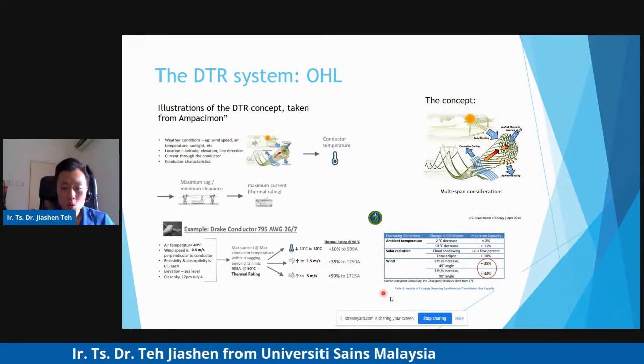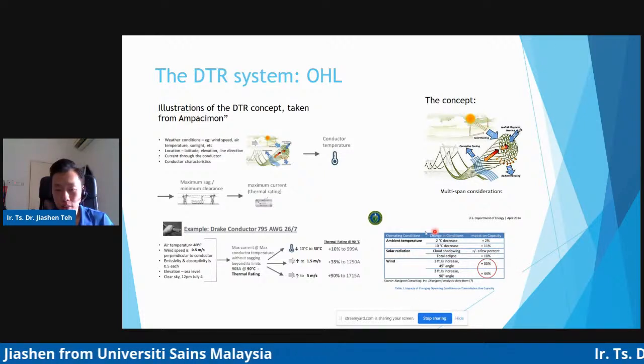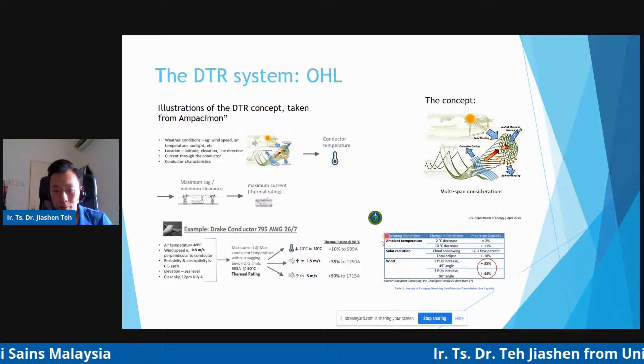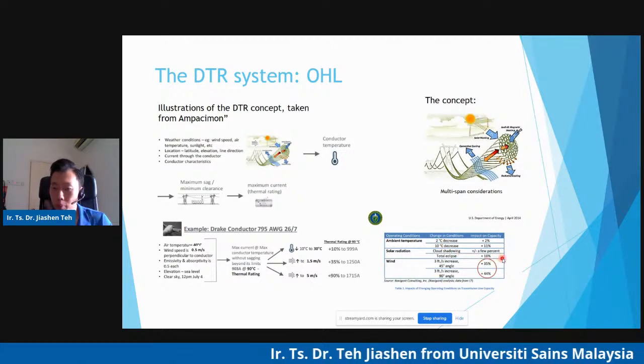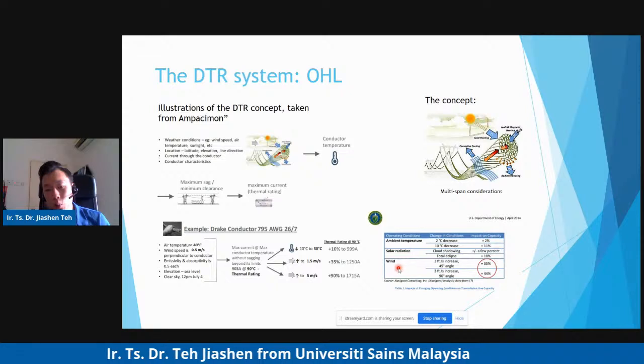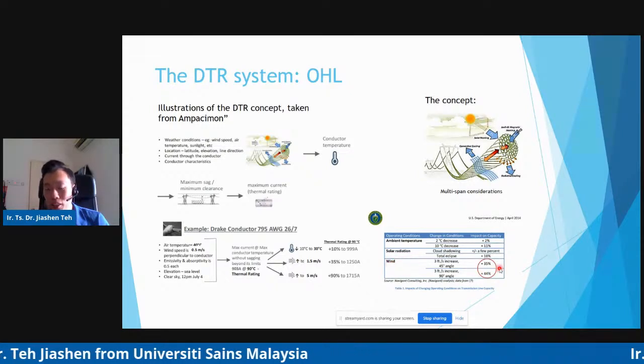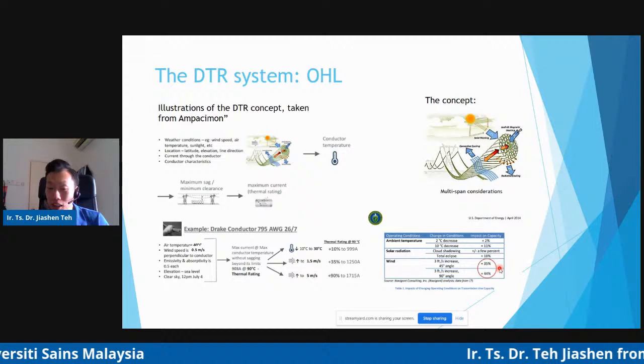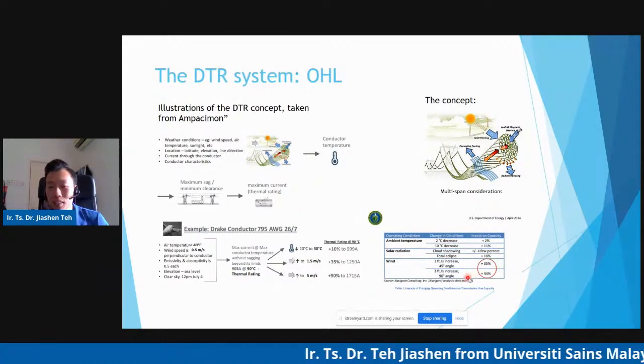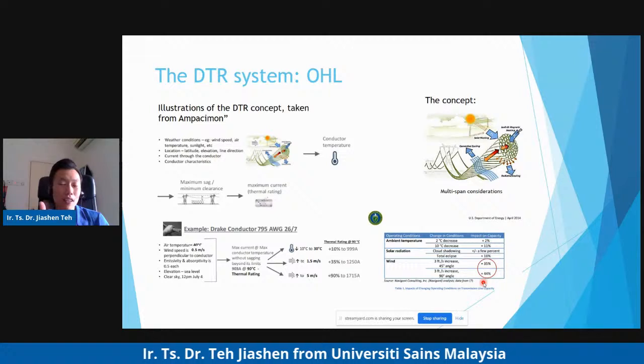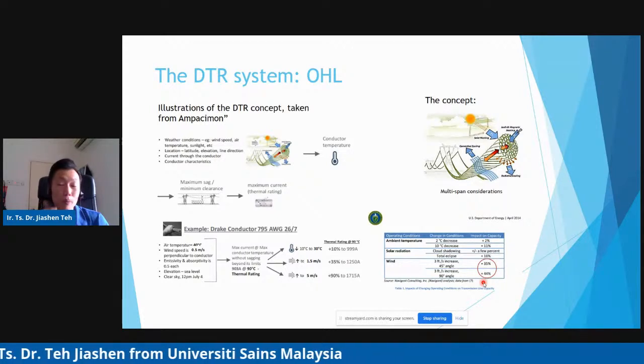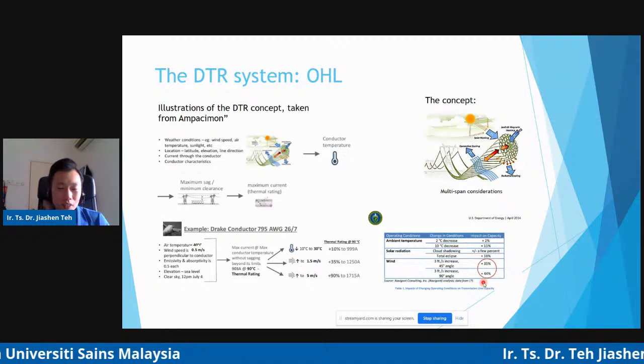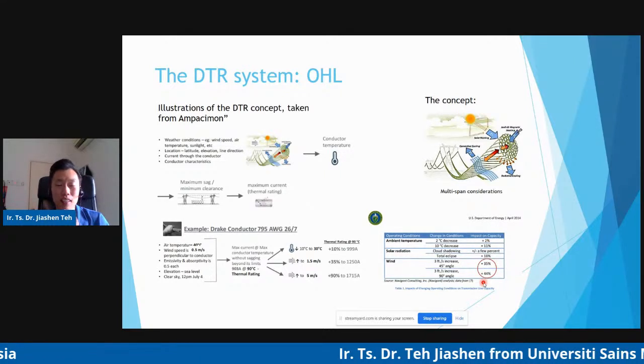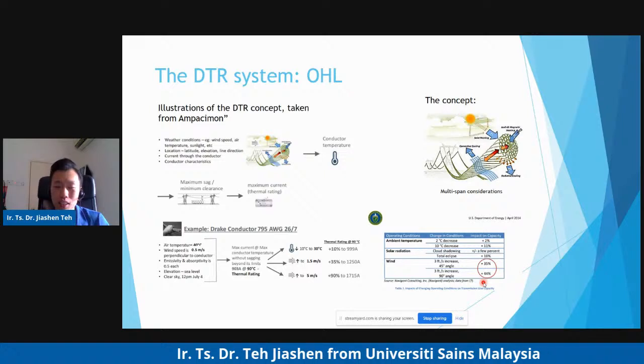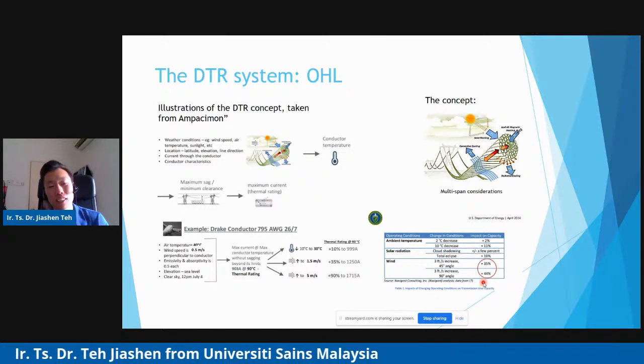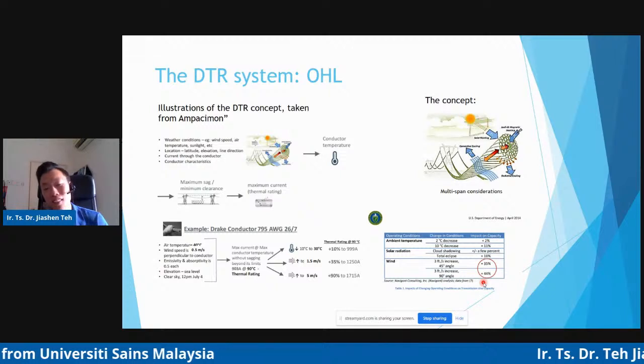I want to point out a study from the U.S. Department of Energy. It shows that with wind considered, we are able to increase line rating capacity by up to 35%, and in certain cases 44%. That represents a significant increment in the underlying unused rating of the conductor, just by deploying the right technology, which in this case is the DTR system.